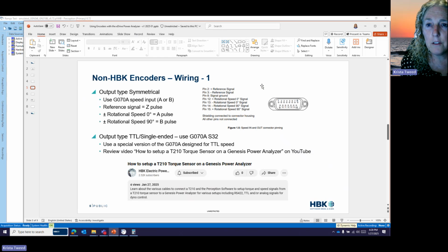Here's the pinout for that connector on the G70. And just to help translate the language that's there on the pinouts, the reference signal is the Z pulse of the encoder. Your rotational speed 0 is the A pulse, and your rotational speed 90 degrees is the B pulse. A lot of times on other data sheets, you'll see ABZ as your different connections.